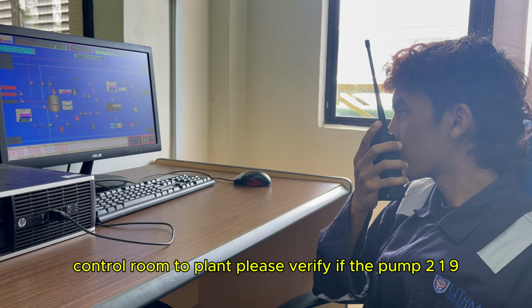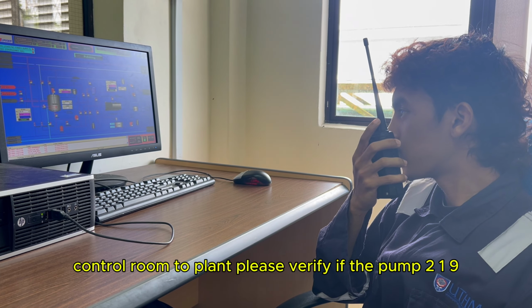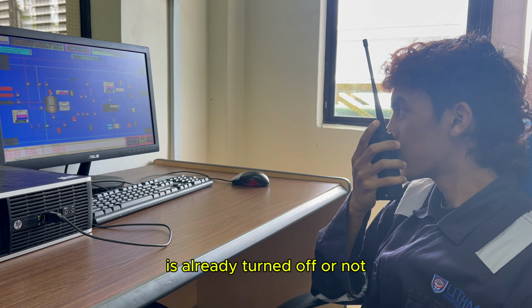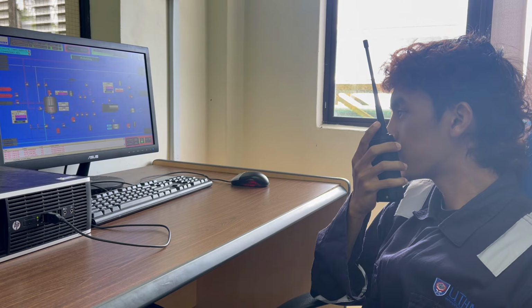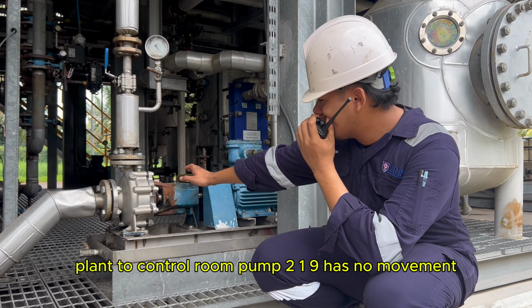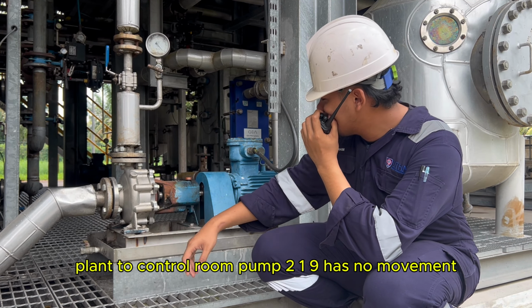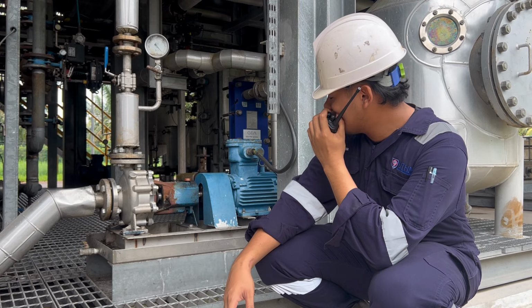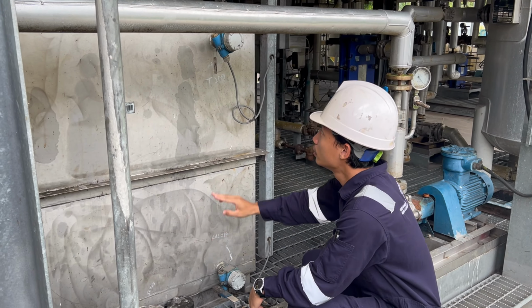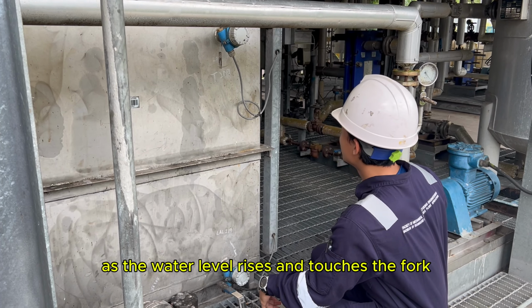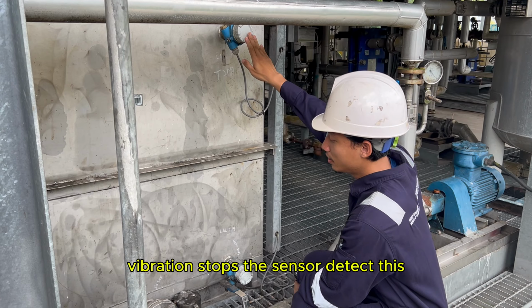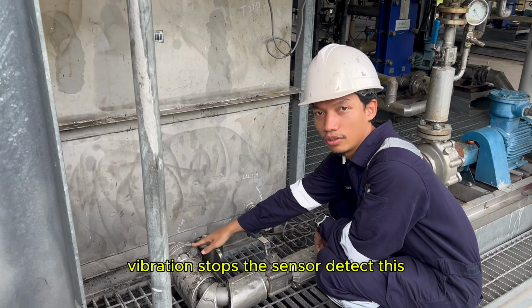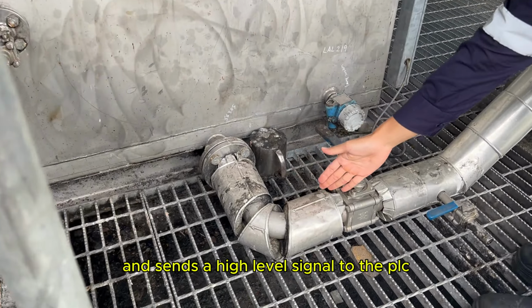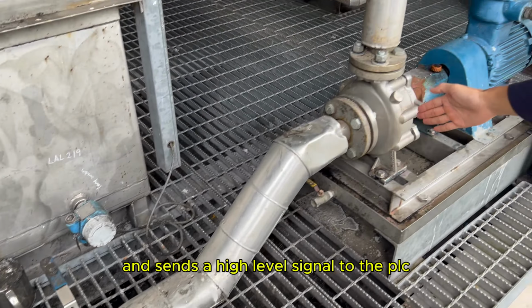Control room to plant, please verify if pump 219 is already turned off or not. Plant to control room, pump 219 has no movement. As the water level rises and touches the fork, vibration stops. The sensor detects this and sends a high level signal to the PLC.